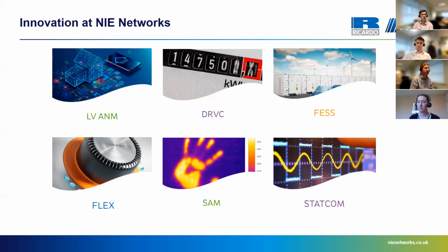The SAM project is looking at a couple of different methods of how we can enhance the thermal ratings of our assets. A lot of our overhead lines and transformers would have a fixed rating, and there's a lot of assumptions built into that. But perhaps on a cool day or a windy day, we could get more out of those assets under certain circumstances, and by managing that in a smarter manner.